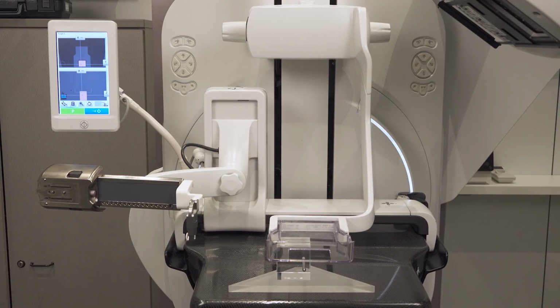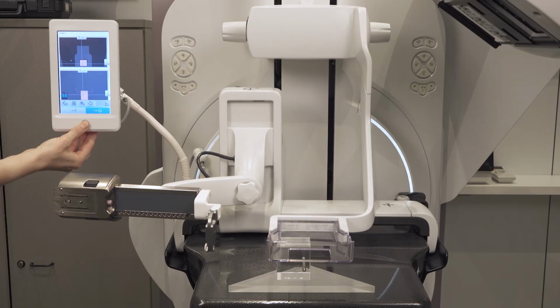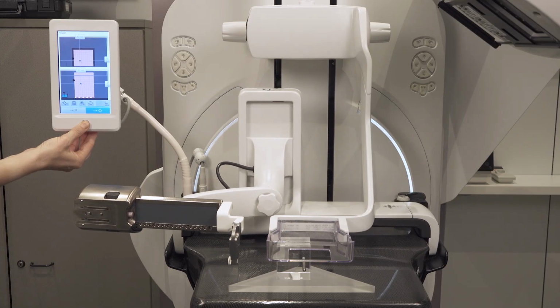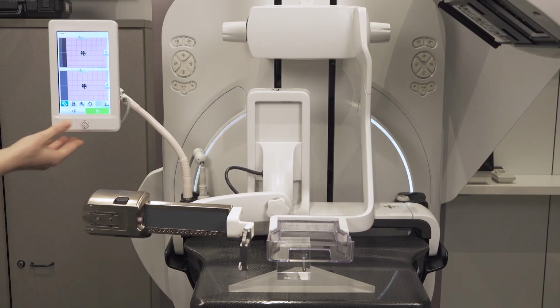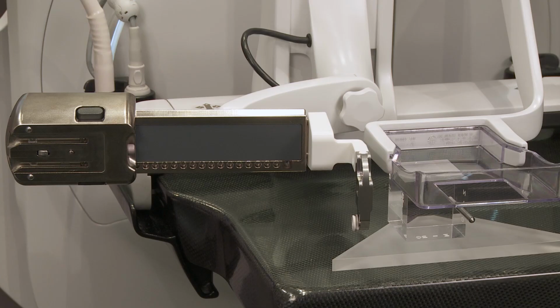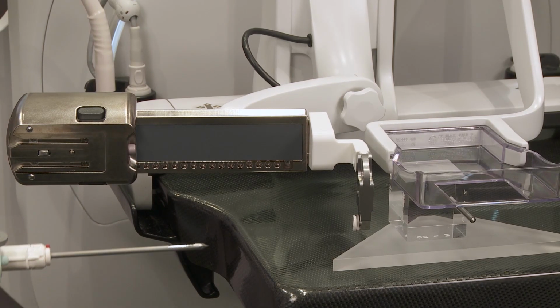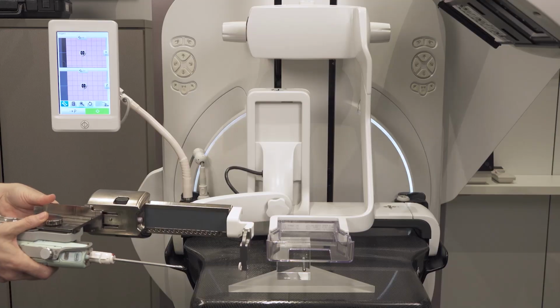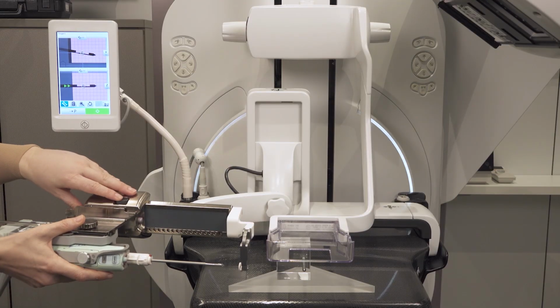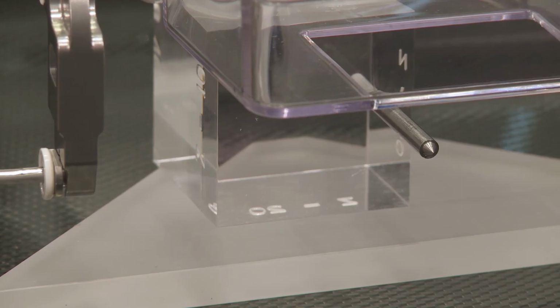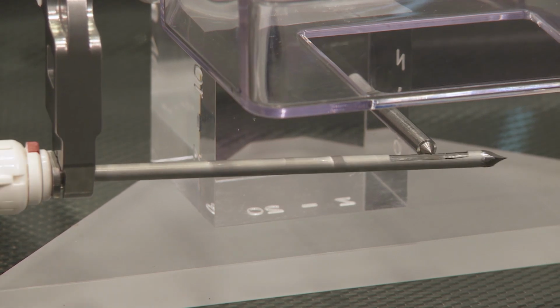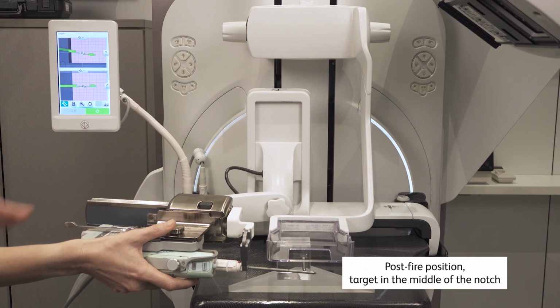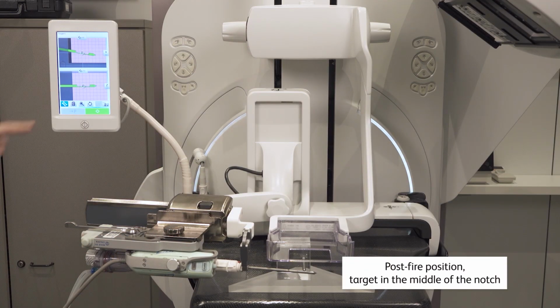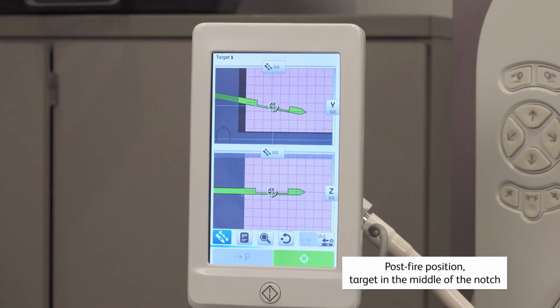The target button is highlighted in blue. Press the screen hardware button to drive the biopsy head to the target coordinates. Attach the probe with its adapter to the slider and slide it all the way. The needle goes through the needle guide. The tip of the pin phantom should be about in the middle of the notch.